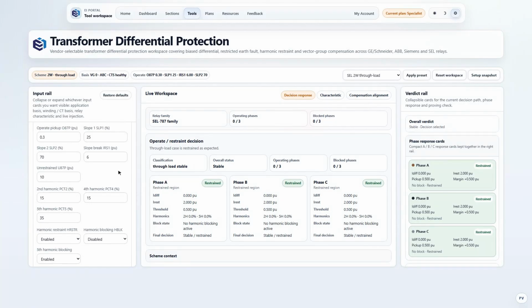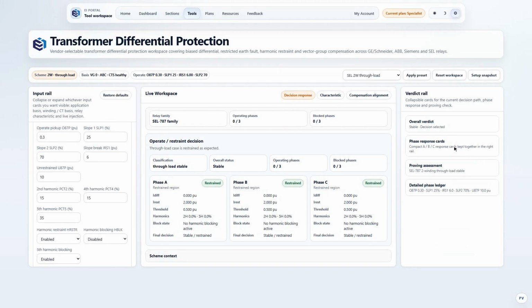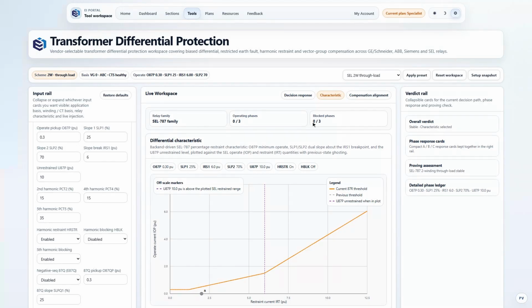So let's apply the through-load case, where a healthy relay must simply sit still. Restraint reads 2.0, giving an operating threshold of 0.5, and the differential current is 0. The vector group rotation and zero sequence filtering line the star and delta windings up so the currents cancel exactly, resulting in a stable scheme. Here's the characteristic doing that work. The operating point sits on the floor of the restraint region, hard against the axis. Everything that follows lands somewhere on this dual slope.